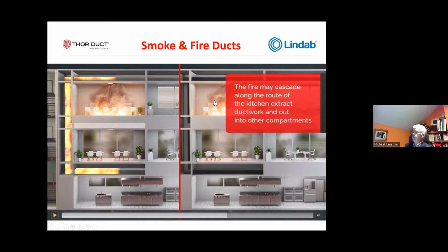Here we have a scenario where the kitchen extract duct is passing through the building and it's passing through a compartment where the fire is. You can see it here. If it is uninsulated, you're going to have this grease ignite. If the grease ignites, it'll ignite like fuel along the entire length of the duct and come back into the kitchen. So it's really important where kitchen extract passes through compartments that it's insulated, like in the scenario on the right-hand side, to prevent the grease igniting.